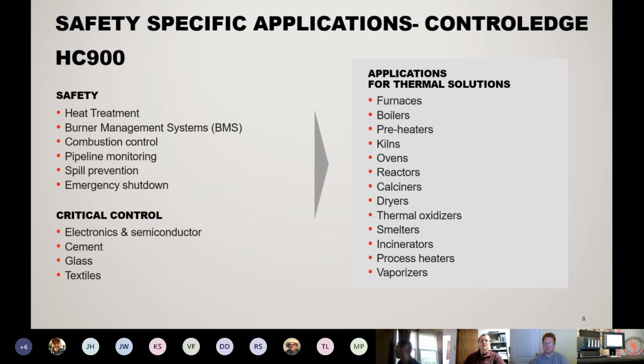So there's one project that we just did, a large heat treat facility that had nitrogen, H2S, HCl, O2 monitoring throughout the plant. And what we did was we used the HC900 controller as a safety controller, communicating to all of the LEL and gas detection sensors throughout the plant. And then if any one of those sensors was to go off because of an unsafe level, it sends a signal to the building management system. The building management system then takes the appropriate actions of opening dampers, turning on blowers, things of that nature to evacuate that unsafe level in that particular area. So that's just one other way that you can use the HC900 in a safety application.